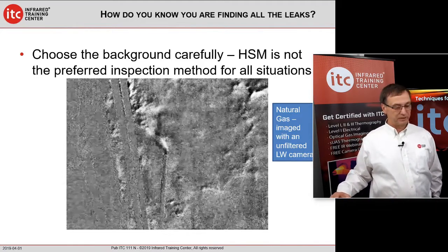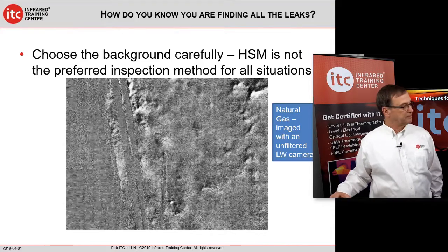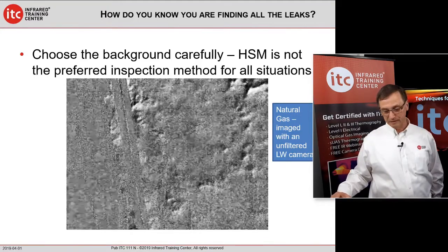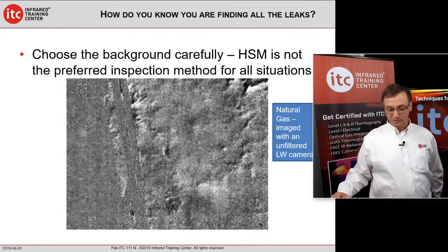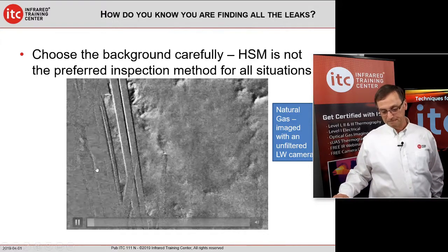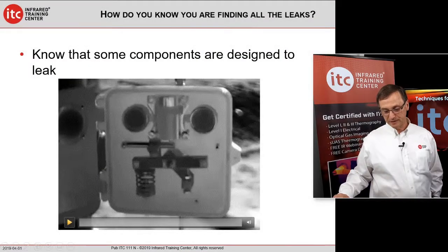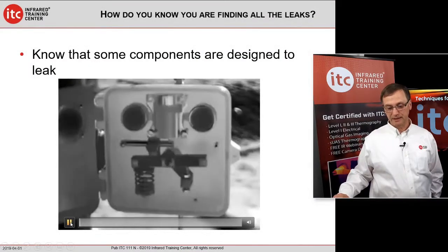Okay, and this would be very typical of an image that you would get from the GF77 of that particular leak. And we can see changes in moisture, wind going by. And so it's just another way to take a look at a leak.